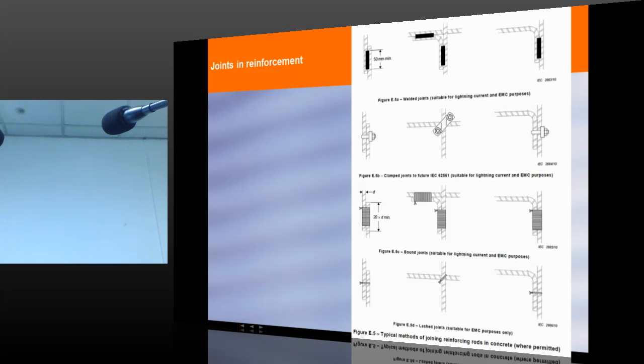I hope it's clear. The limitation is over the rebar, an extra down conductor inside the building, instead of the natural conductors. What is recommended is to use the naturally available rebar. But once we explain this to the civil engineers or structural engineers, theoretically it's okay, but practically, once we step into it, there will be restrictions. People say, no, I will not allow, I have some special requirements and so on. To satisfy some of the additional requirements, the standard recommends to use an additional conductor. But from a lightning current point of view, structural steel or the rebar itself is enough, provided it is connected with the conductors which are tested.